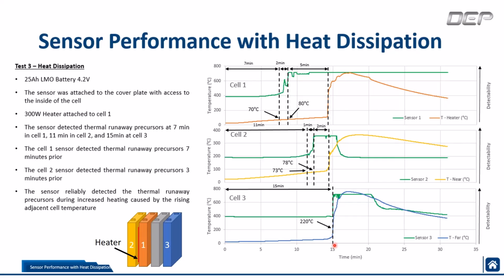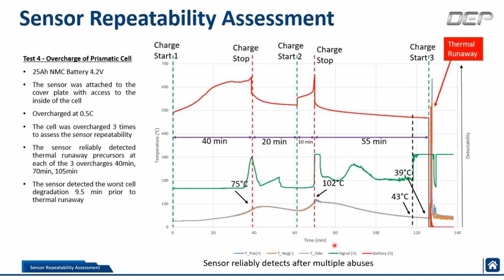Now, in this next test here, which is a lot more interesting, what we did was an overcharge, but not a simple overcharge. We actually repeated the overcharge, stopped and continued it several times over. So in this case, we used a 25 amp hour NMC battery, and we pushed it into overcharge at half C. You can see this red line here is the battery voltage. This green line here is our sensor signal. And down here, we have the thermocouples that we placed on the positive, the negative, and the side wall.